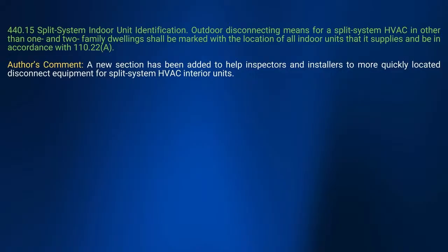Ryan Jackson actually did a whole thing on this—funny, because he said it's a single piece of equipment. There's a whole section in the code that says if it's a single piece of equipment, once you disconnect that 240 volt on the roof, you're in an electrically safe work condition. You don't need a disconnect for the 110 volt down below. But they're always trying to require us to have a disconnect down below.